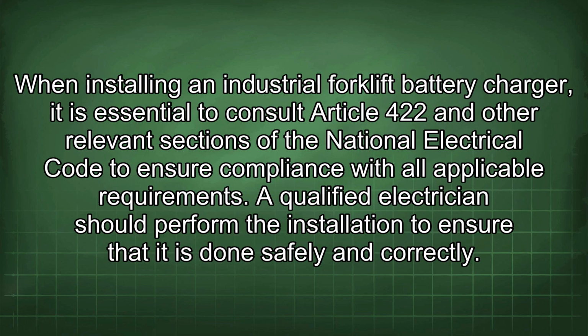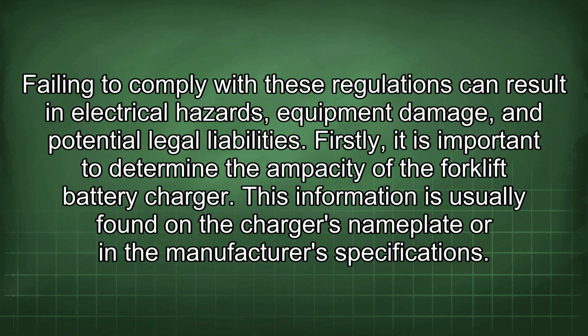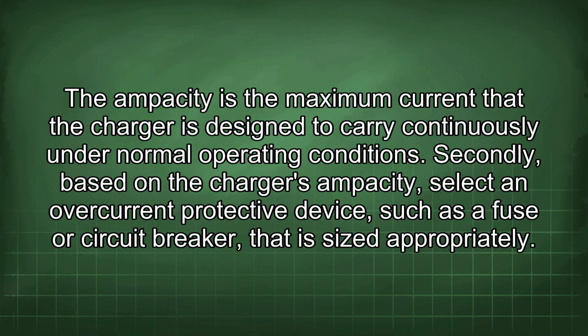When installing an industrial forklift battery charger, it is essential to consult Article 422 and other relevant sections of the National Electrical Code to ensure compliance with all applicable requirements. A qualified electrician should perform the installation to ensure that it is done safely and correctly. Failing to comply with these regulations can result in electrical hazards, equipment damage, and potential legal liabilities. Firstly, it is important to determine the ampacity of the forklift battery charger. This information is usually found on the charger's nameplate or in the manufacturer's specifications. The ampacity is the maximum current that the charger is designed to carry continuously under normal operating conditions.